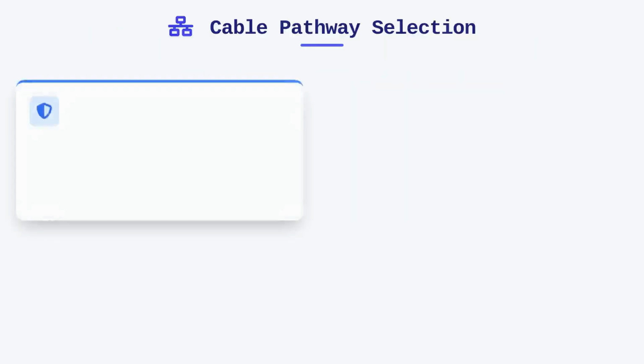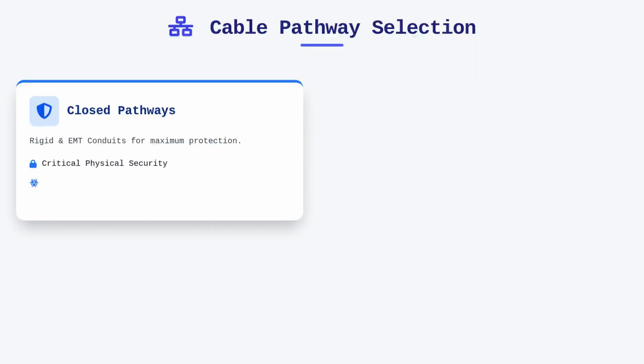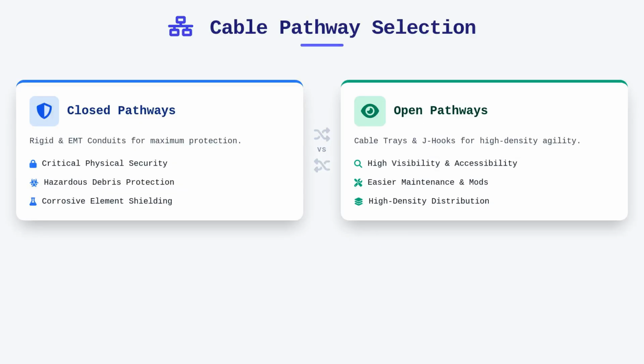The choice between continuous closed pathways, like rigid and EMT conduit, and open accessible pathways, such as cable trays and J-hooks, depends entirely on the unique requirements of the deployment environment. Closed pathways are mandatory where physical security is paramount or where the environment contains hazardous debris or corrosive elements that could damage the cable sheath. Conversely, open pathways offer the visibility and accessibility necessary for high-density horizontal distribution, allowing for easier maintenance and modifications.